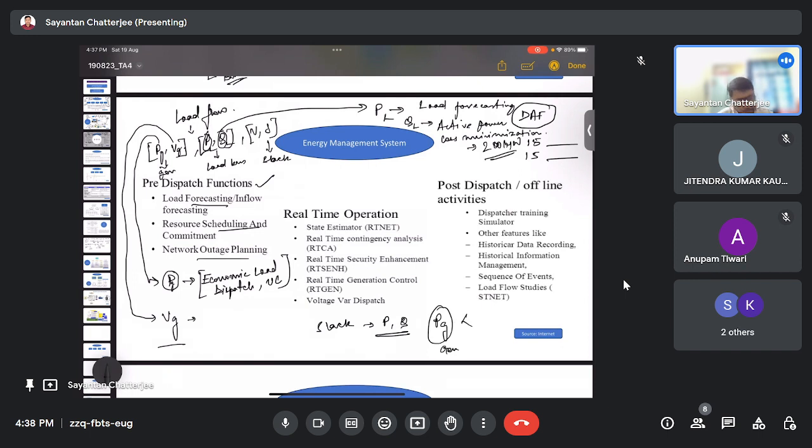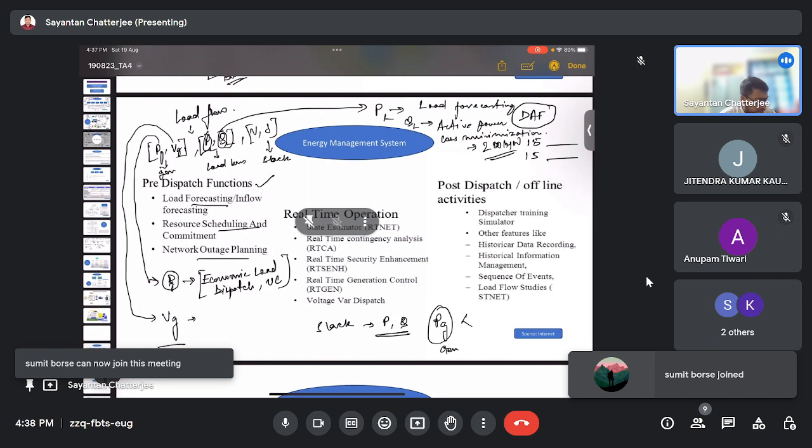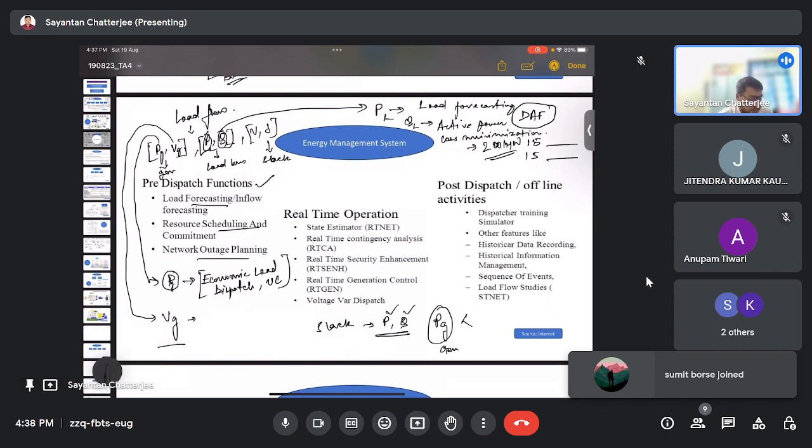If we consider only the case of the slack bus, its main purpose is to deliver the remaining or resultant loads as well as the system losses, line losses and all these things in the system. So that's why this P and Q are kept unknown. The entire value that can't be delivered by the other generator buses would be delivered by the slack bus.